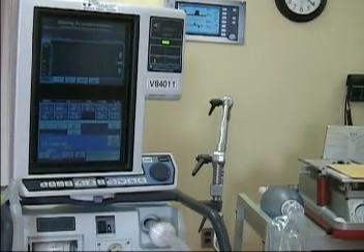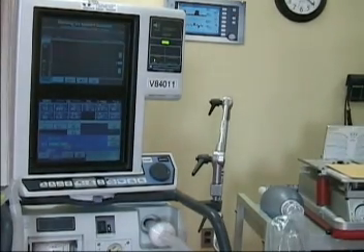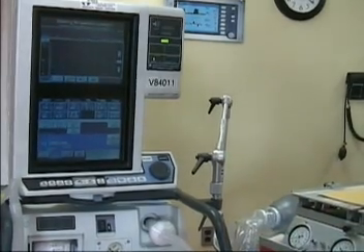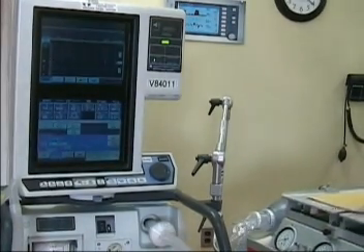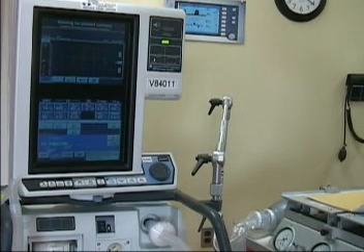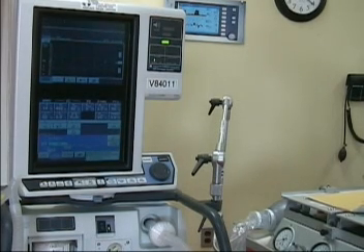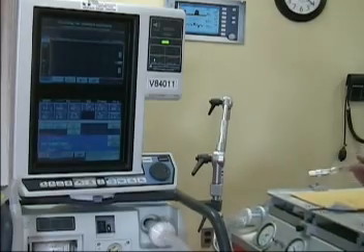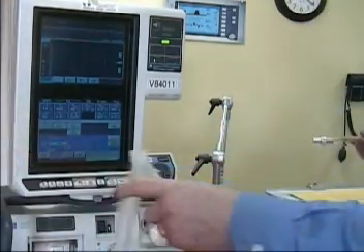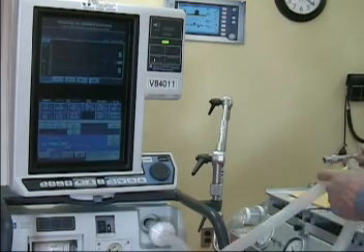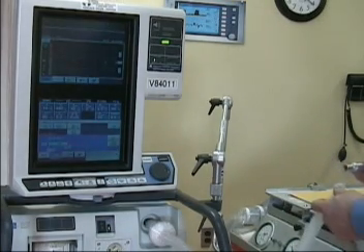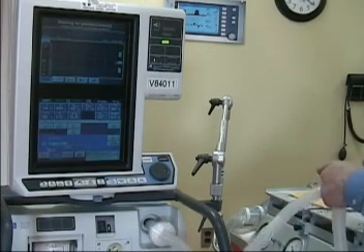So our patient arrives. I'll move my test lung so we can see it. And then we're going to connect the ventilator to my test lung. As soon as the ventilator is connected to the test lung, it will start ventilating.